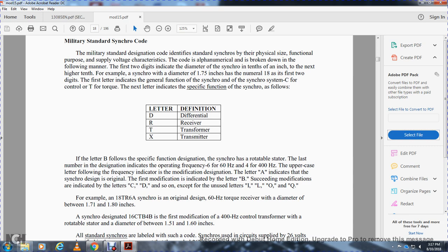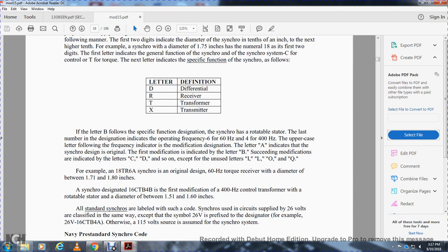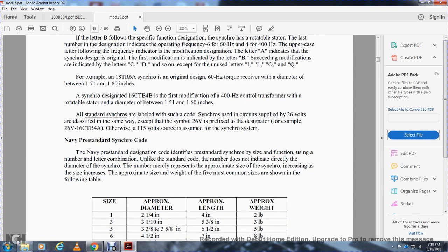The pre-standard synchro designation code identifies pre-standard synchros by size, function, and letter or number combination. Unlike the standard code, the number does not indicate the diameter directly but indicates the approximate size, with increasing numbers indicating increasing volume and size. The pre-standard size designations and approximate standard equivalents are shown in the following tables. Size 1 is approximately 2¼ inch diameter, 4 inches in length, and 2 pounds. Size 3 is 3 and 1/10 inch diameter, 5 and 3/8 inches in length, 3 pounds. Size 5 is 3 and 3/8 inch diameter, 6½ inches in length, 5 pounds. Size 6 is 4½ inch diameter, 7 inches in length, 8 pounds. Size 7 is 5 and 3/4 inch diameter, approximately 9 inches in length, and 18 pounds.